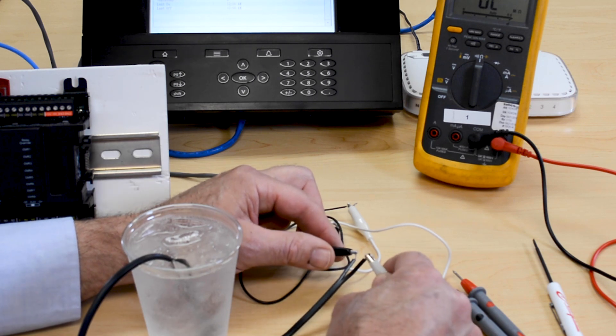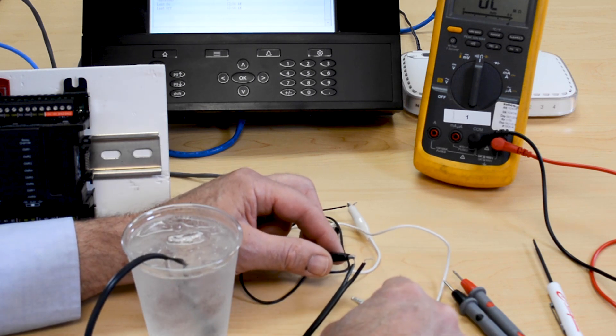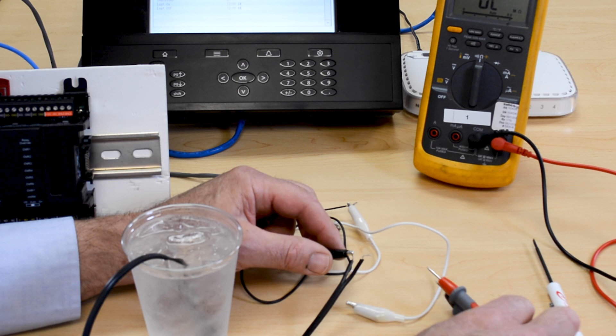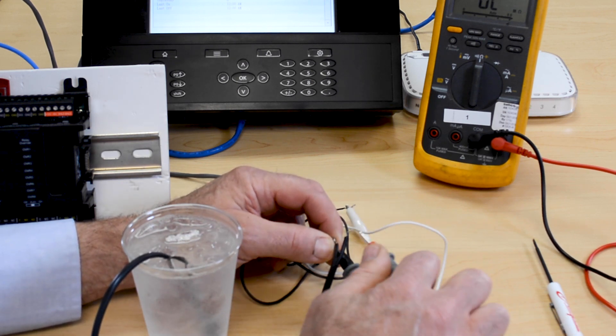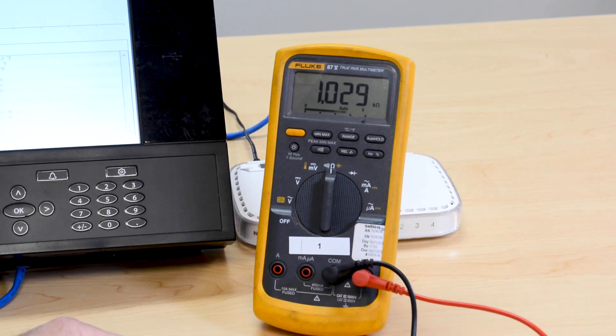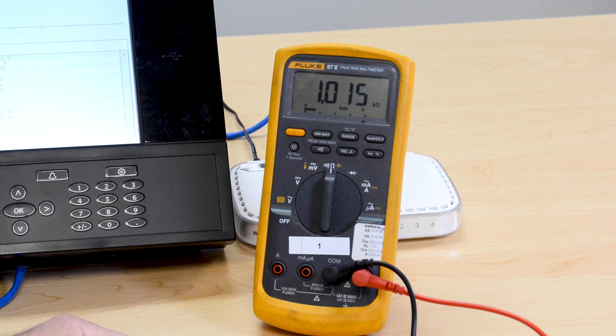I will remove at least one of the two wires and I'm going to take my meter and put it across, looking for it to show me somewhere very close to a thousand ohms. Because I know from that chart that a thousand ohms has me very close to 32 degrees. That's an excellent indicator that the sensor itself is good.